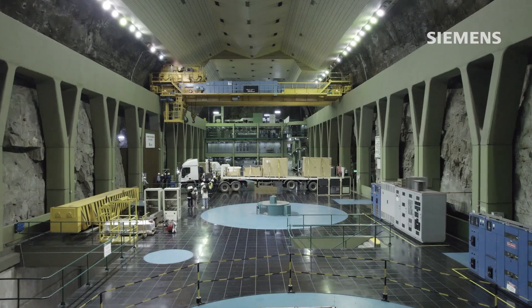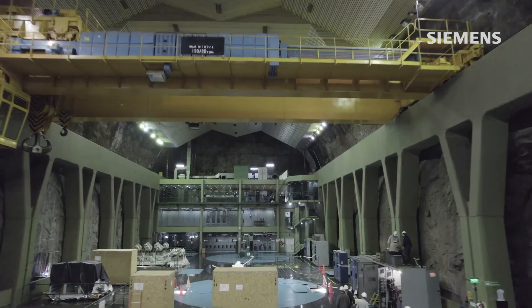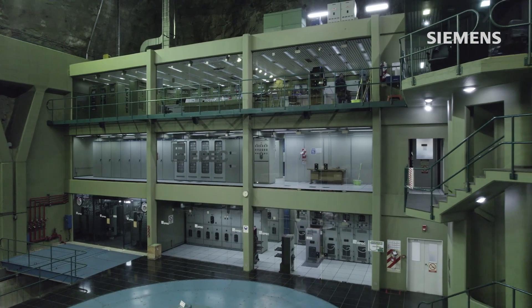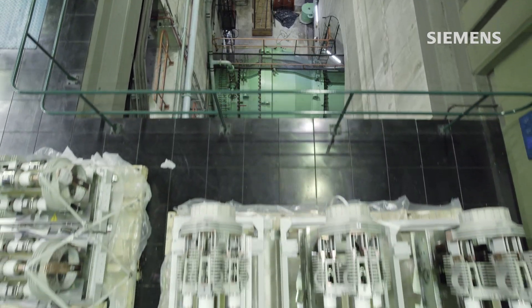The four existing generator circuit breakers have been upgraded with Siemens HB3C Compact Circuit Breaker Modules with a breaking capability of 106 kA. For the converter switchgears, two HB3C units have been integrated into two completely new VB1 switchgears.